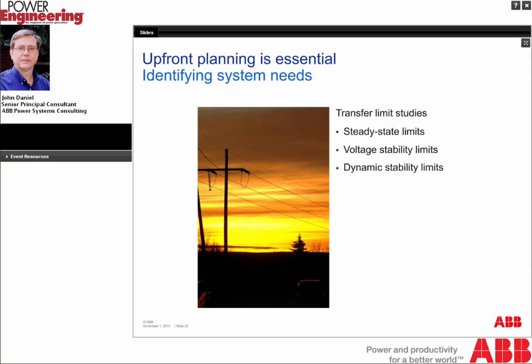And then finally, the transfer limit studies. The utility that I spoke of earlier, when they did the study, the conclusions of the studies indicated that the biggest impact associated with the retirement of their plant was not the loss of local voltage support, but a degradation in the regional transfer capability. So in other words, retiring their plant would adversely impact the amount of power that could be imported into the region that the plant was located.